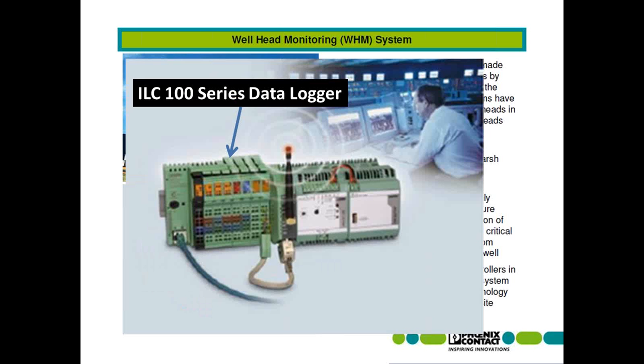It's an application using our ILC 150 series controller. It's preloaded with application function blocks for recording data. We can configure this unit to capture multiple points of data, recording trends and changes for as long as 35 days, saving information in the form of a hard card, and allowing you to upload the data up to the network, or manually pulling the card and inserting it in a computer at the pad site.